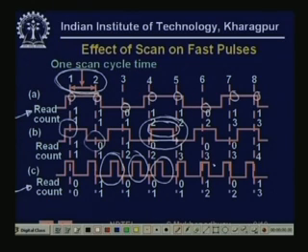So there will be more of a chance that this pulse will not be counted, this pulse will not be counted, and you will get drastic errors. For example, in this pulse, when it was sensed here it was 1, when it is sensed here it is also 1. So therefore it will be assumed that it continued at 1. So in this case the pulse count will be severely wrong. It will assume that it has continued here, and then it is continuing here, and then here, and then at this point it rises. So the count will be a small fraction of the real speed, and we are going to be totally out.